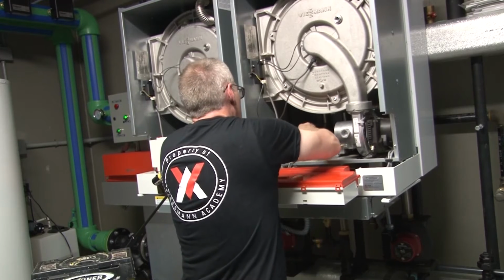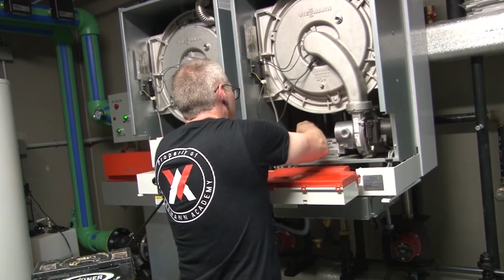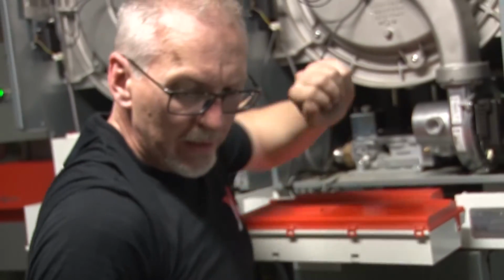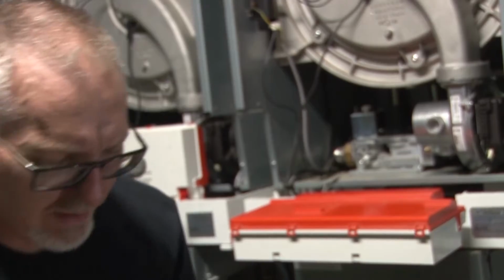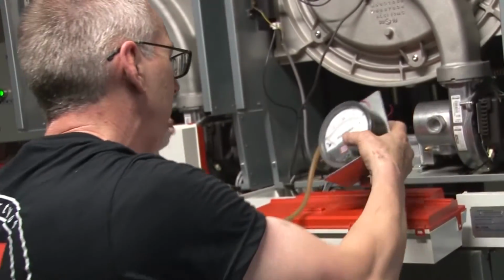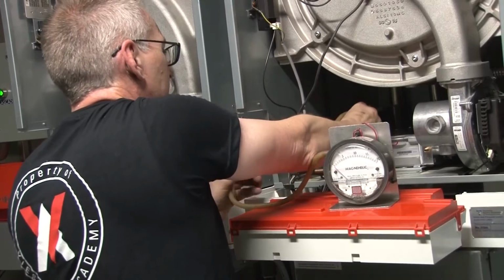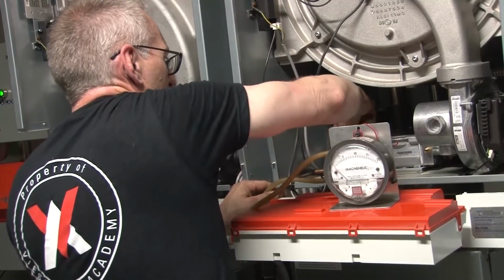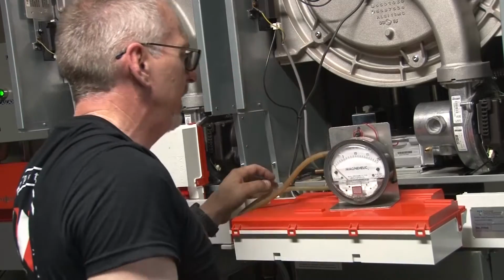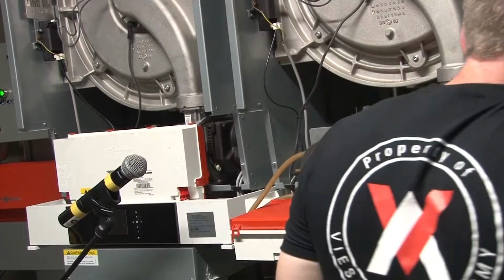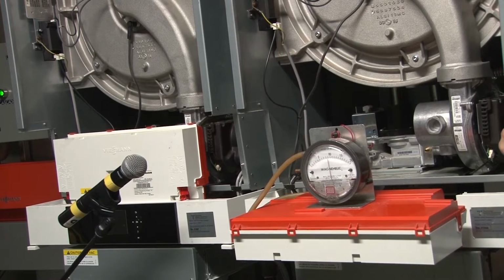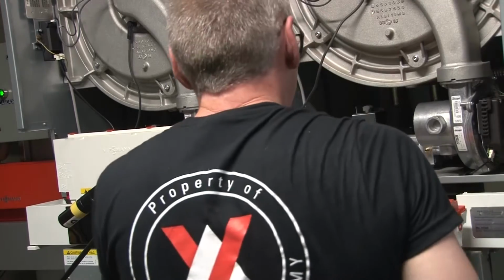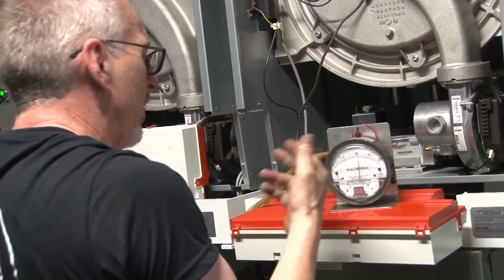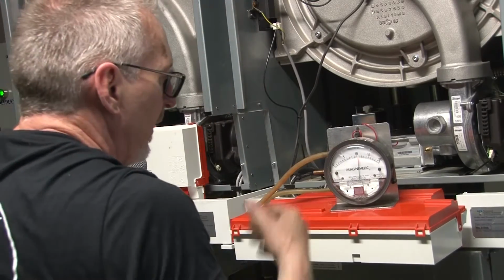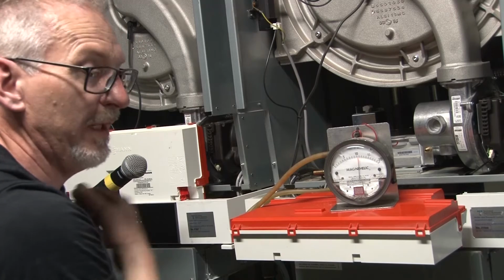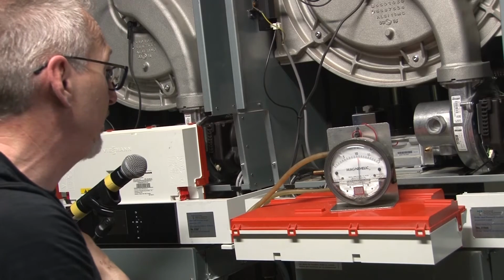I've got that back in there. I'm going to give that just a back it off a turn. I don't want to pull it all the way out. And then I have my gas pressure gauge. I use a magnehelic gauge. I like these because they give me a good idea of gas fluctuation, pressure drops, those types of things. I'm going to put that on my gas valve and I turn the gas on. There we go. And in the manual it's going to say you don't start the boiler if you're below 4 inches on your pressure or above 14. So we're pretty good to go here. We can fire this boiler.